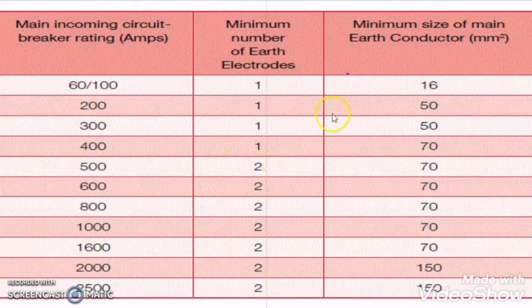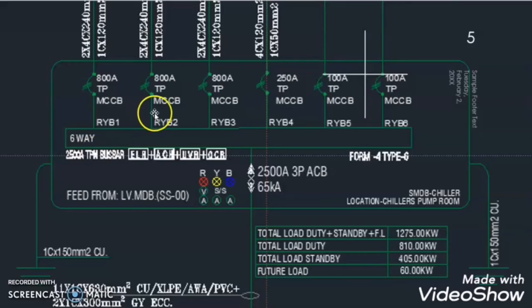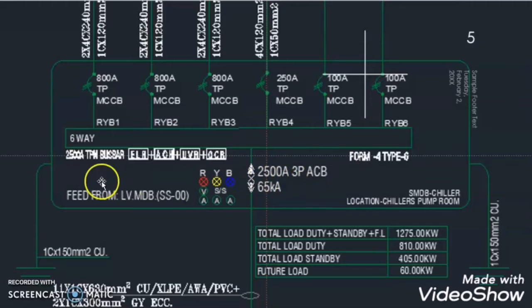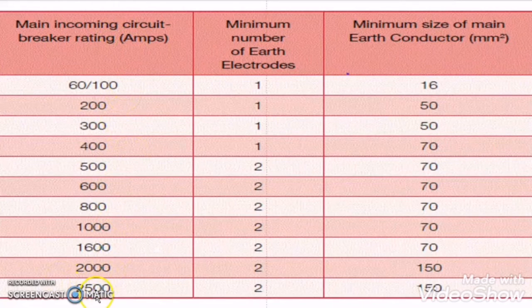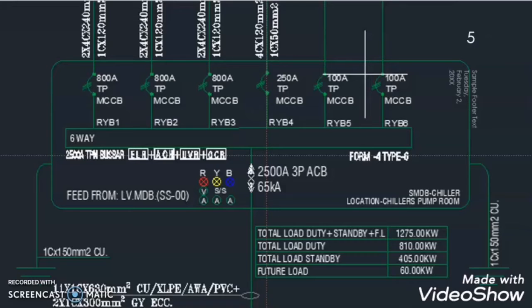Let us take some examples in order to select the minimum size of the main earth conductor. Here is the first example. The main incomer rating of this LV panel is 2500 ampere. So as per this chart, when the main incomer breaker rating is 2500 ampere, then two pits are required and the size of the main earth cable will be 150 square mm. This is the pit symbol, and the minimum size of the cable here is mentioned as 150 square mm copper cable.